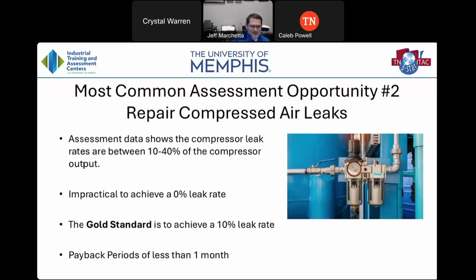So our assessment data has been showing for plants typically leak rates of between 10 and 40% of the compressor output. Now, think about that. Your compressed air is making so many cubic feet per minute. Well, in order to make that cubic feet per minute, only a little less than half of that is actually being used for its intended purpose, if you're at 40%. And I'll tell you that we tend to see leak rates at the plants we visit that are usually between 20 and 40. I rarely see 10% leak rates. They're usually between 20 and 40% of the compressor output.